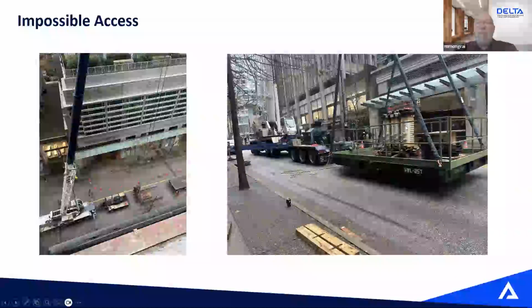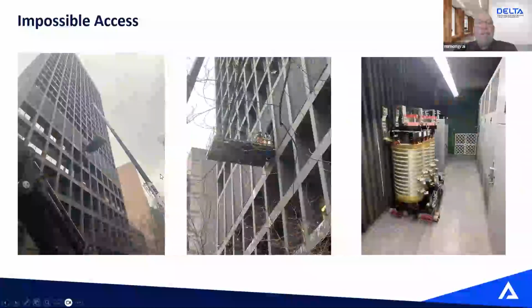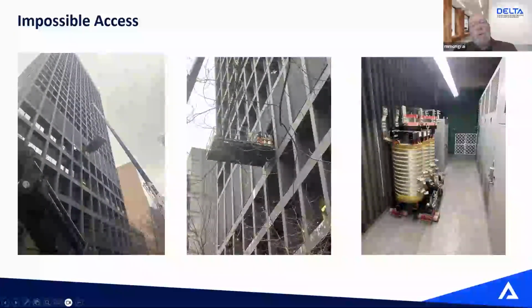They brought the transformer. You see here the core and coil sitting on that massive platform. So the crane lifted the platform to the side of the building where there was a hole made in the sidewall of the building, and then the core and coil was brought into the building using that hole in the sidewall. It's more money, but again, if there's no option of doing the three single phase core and coil, doing anything, that's the only option. So sometimes that's got to be done. We've seen that we have to go from the roof of the building. So we've seen all kinds of situations where we had to do this.